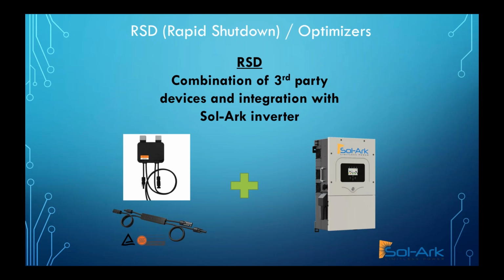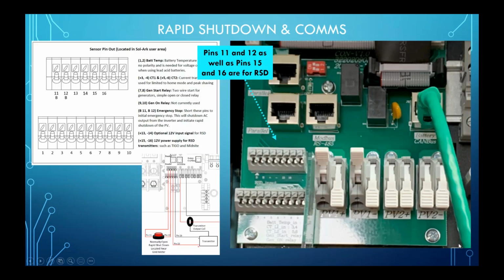And what I mean by the integration is, again, these toggle switches right here, the 2 of them that are lifted up, those are the PV inputs. They go into our motherboard and our inverter. And then to the left of that is this pin out area. In there, pins 11 and 12 are the normally open rapid shutdown relay. So if that relay gets tripped, that is how rapid shutdown physically and electrically happens in the inverter. And then adjacent, in pins 15 and 16, we have an onboard 12-volt power supply for the rapid shutdown transmitter.